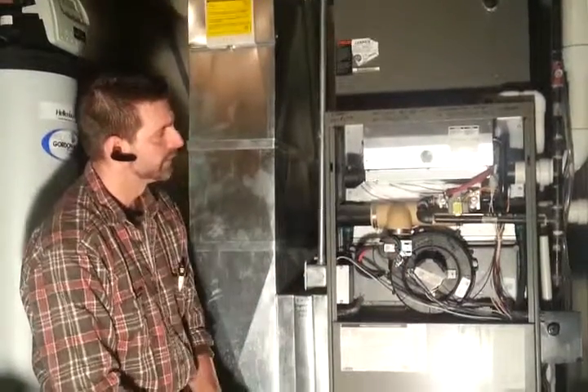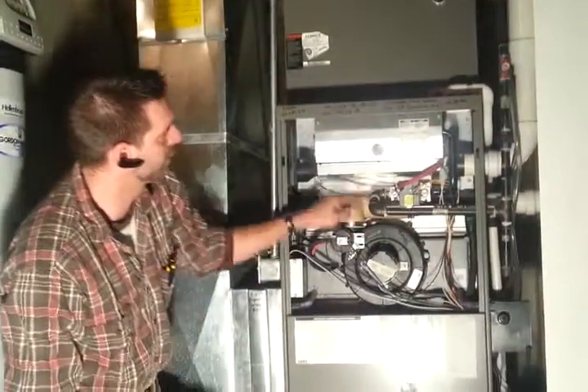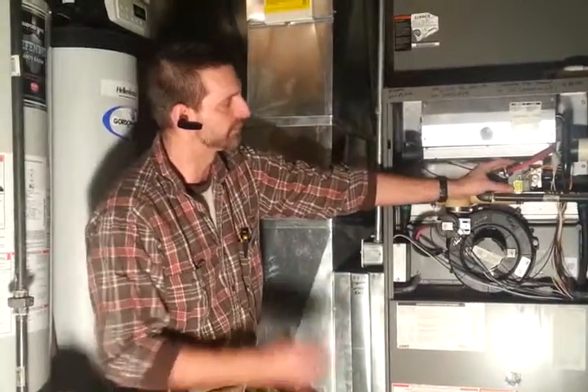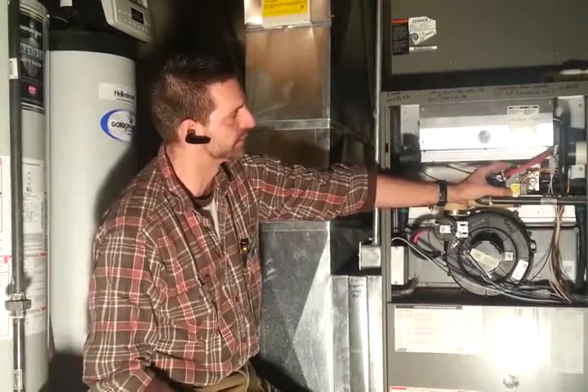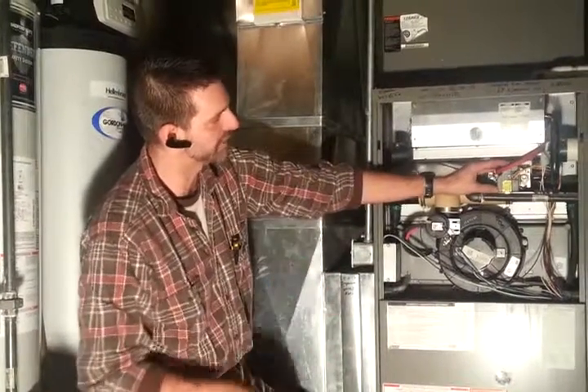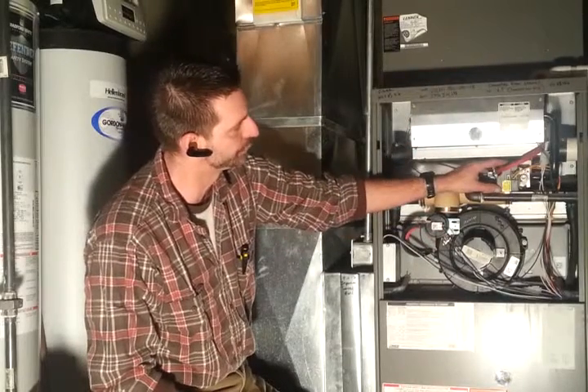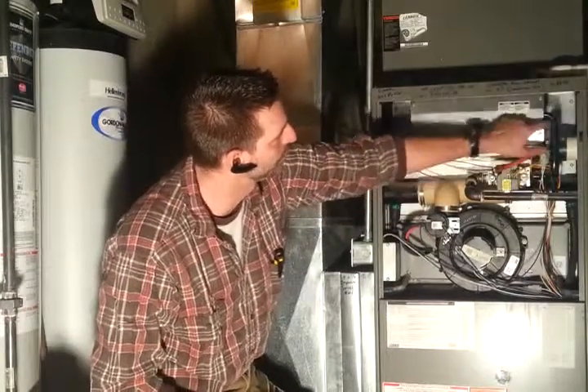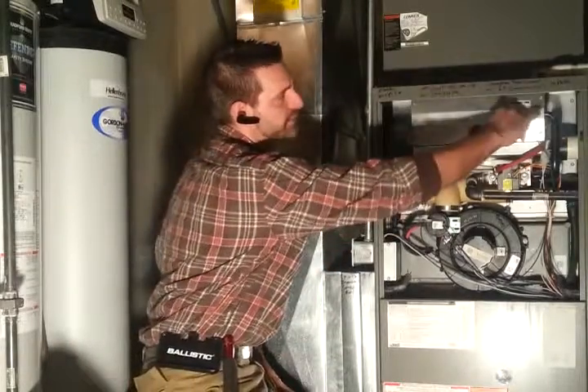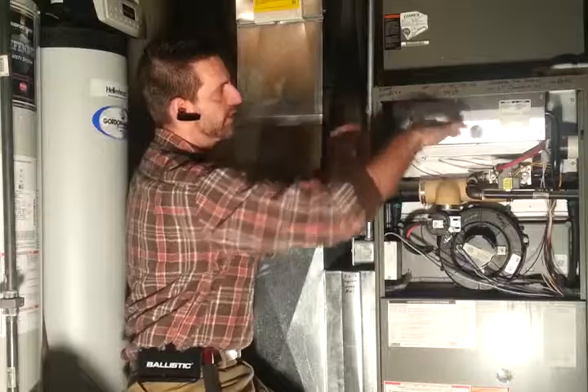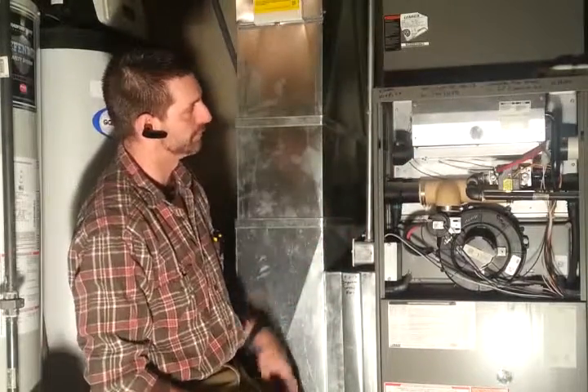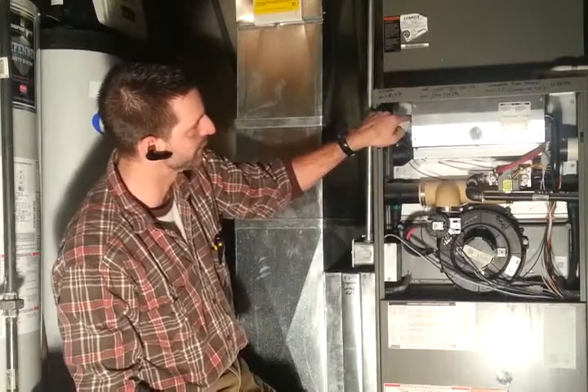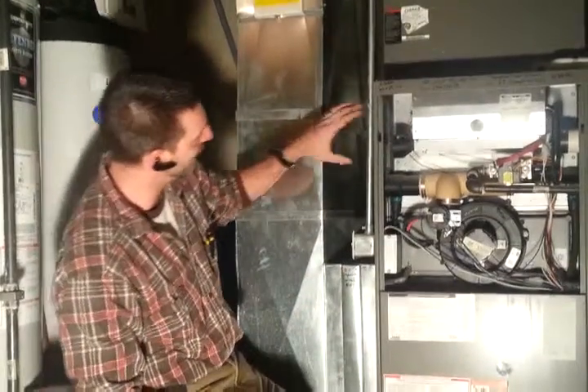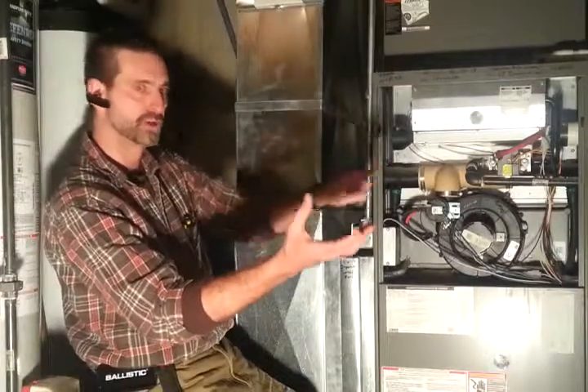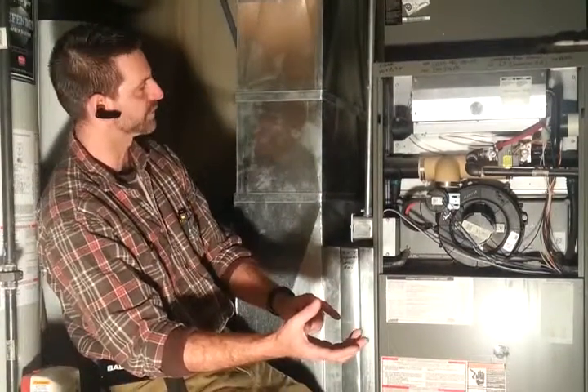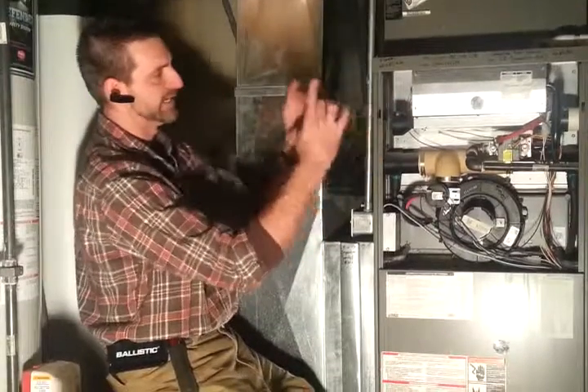Here's my gas valve. As you can see, my gas comes in here, goes to the input side of my valve. There's several things that have to happen. We'll talk about that in later sessions. Basically, your thermostat, as long as all the safeties and everything are happy, will turn your gas valve on, allowing gas to flow up through here, which is called your manifold. And then there's several orifices that take that gas, mix it with air, and it goes across my hot surface igniter, and we get ignition. Once it ignites, we're blowing a nice flame into our heat exchanger. And your heat exchanger, we can't see that, it's behind here, but those are long tubes that run throughout your furnace. That's where we introduce all the heat, and we heat those tubes up.